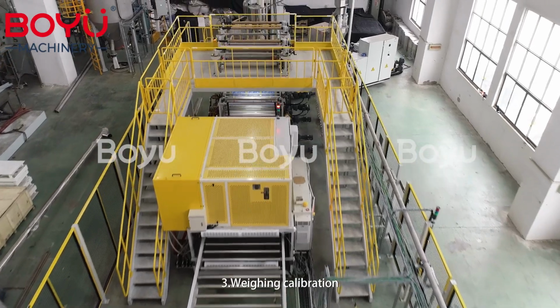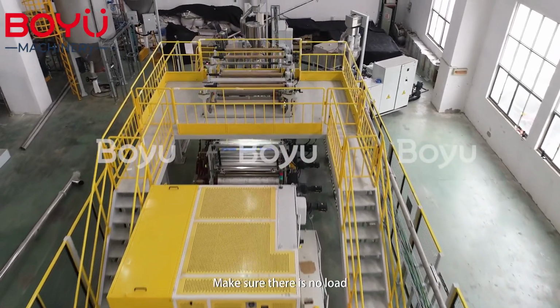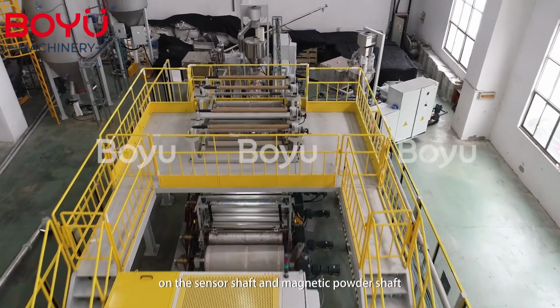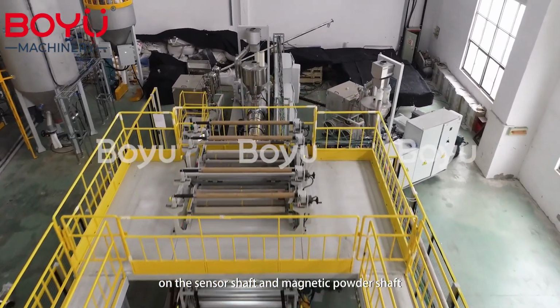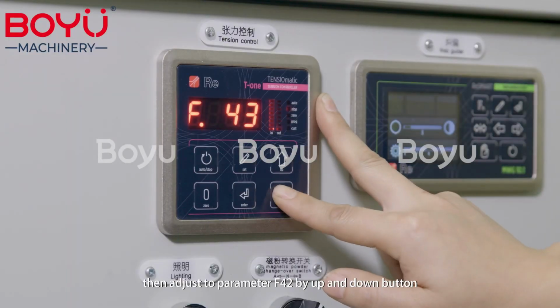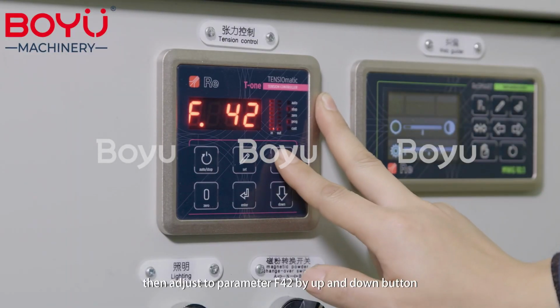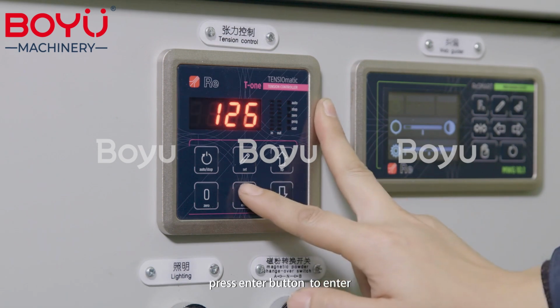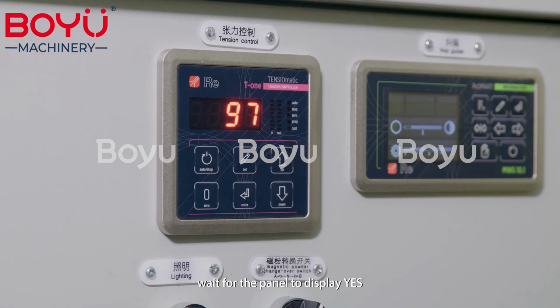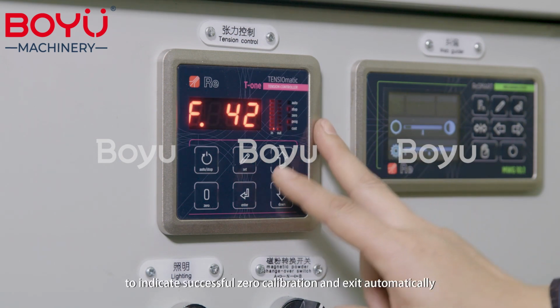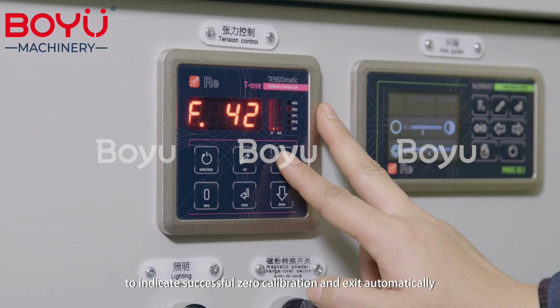3. Weighing calibration. Make sure there was no load on the sensor shaft and magnetic powder shaft. Then, adjust to parameter F42 by up and down button. Press Enter button to enter. Wait for the panel to display Yes to indicate successful 0 calibration and exit automatically.